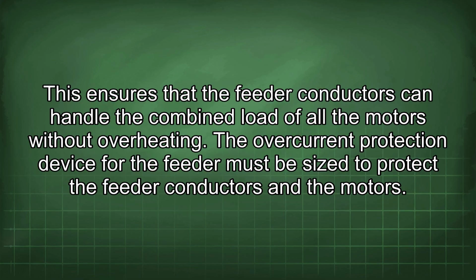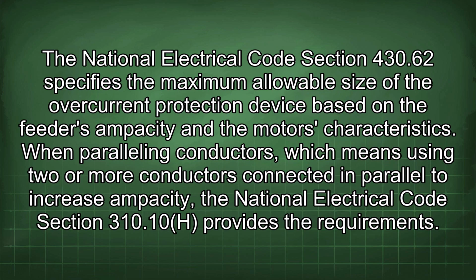The overcurrent protection device for the feeder must be sized to protect the feeder conductors and the motors. The National Electrical Code Section 430.62 specifies the maximum allowable size of the overcurrent protection device based on the feeder's ampacity and the motor's characteristics. When paralleling conductors, which means using two or more conductors connected in parallel to increase ampacity, the National Electrical Code Section 310.10(H) provides the requirements.